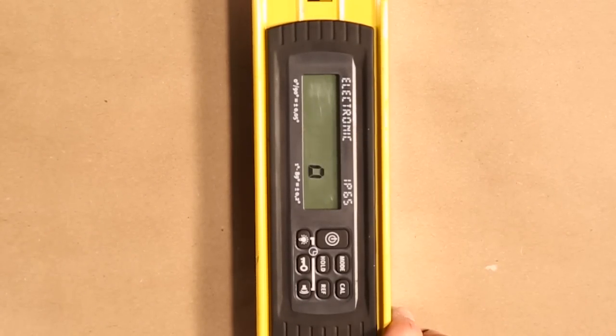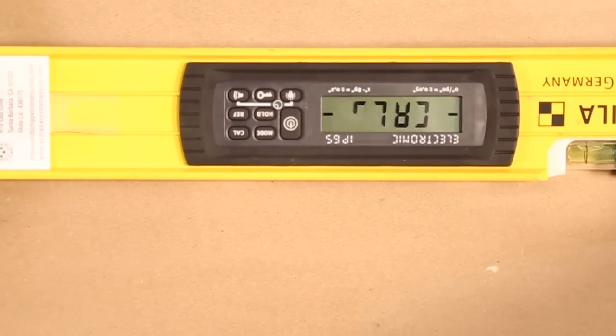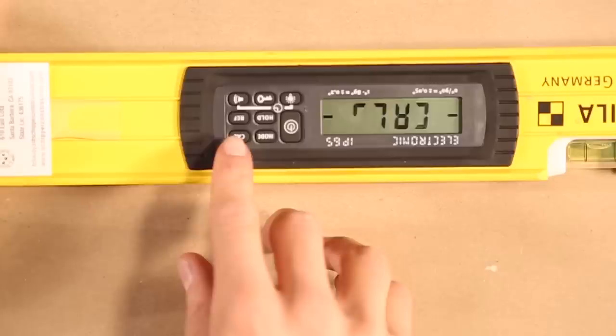You will notice that the second line will stop flashing. That's when you do your second rotation. You're going to center your vial 100%. Hit calibration.